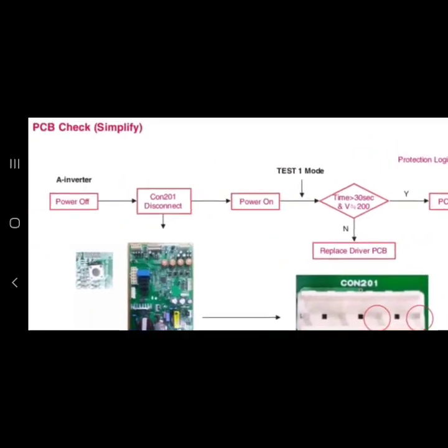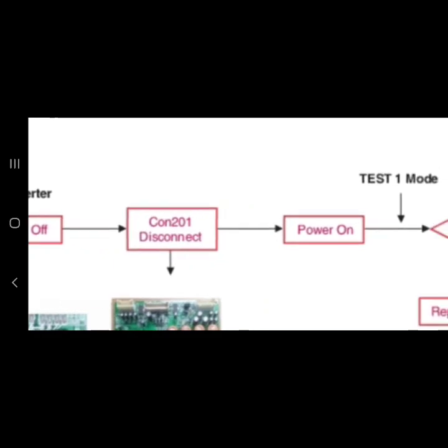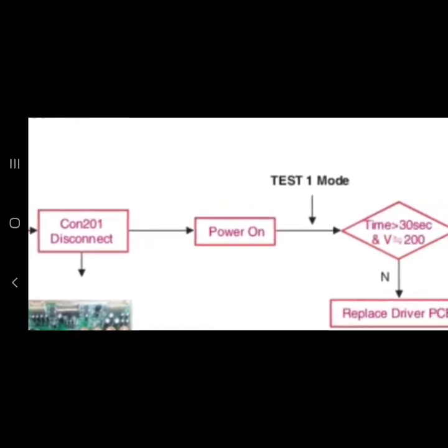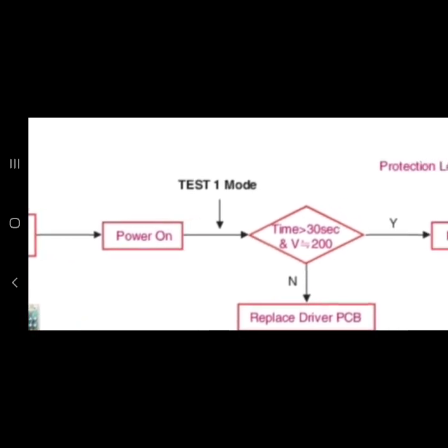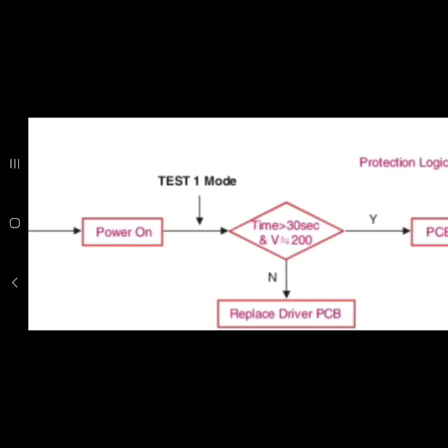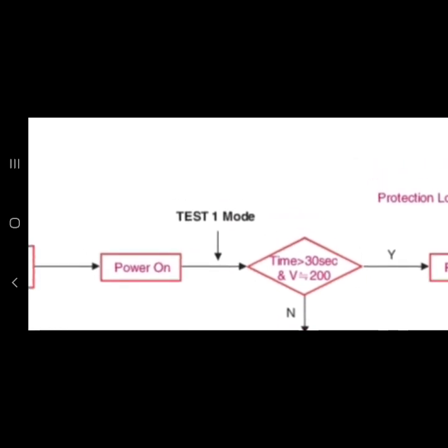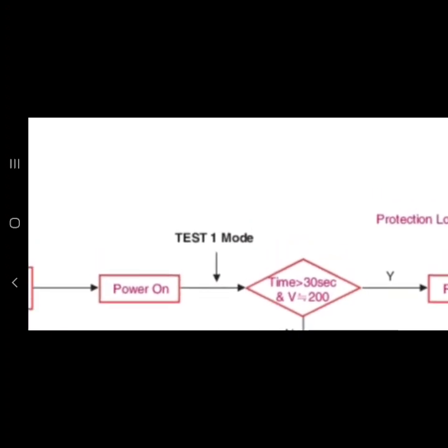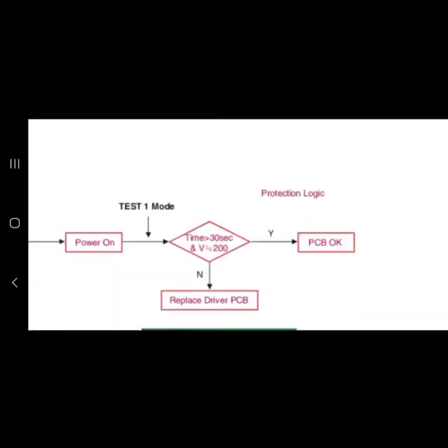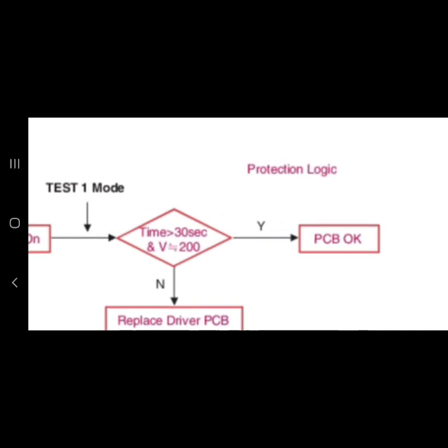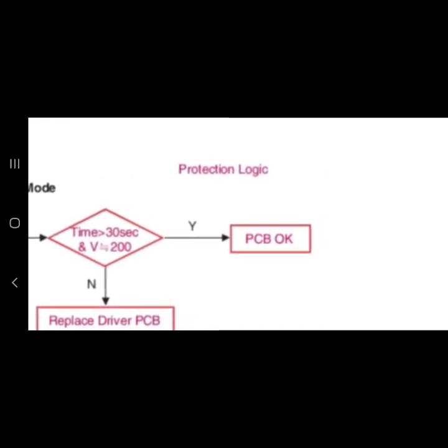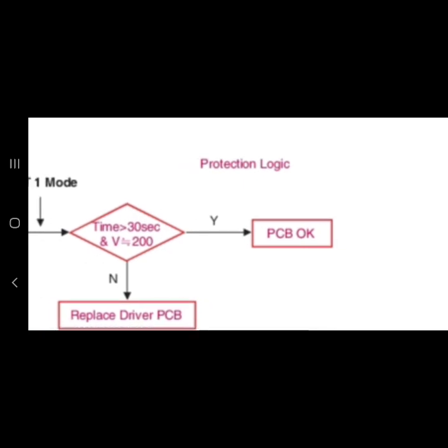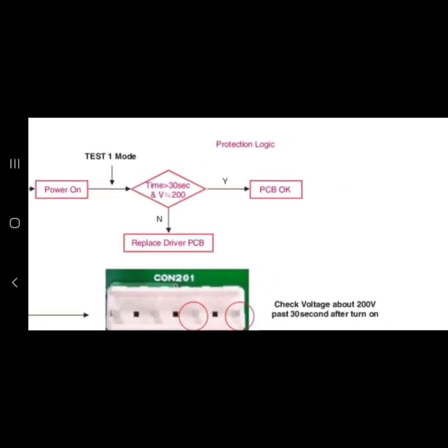Let's think about this. Again, we're going to power off step one, hook up our leads to Con201, which is short for connector 201. We're going to power on the unit and then after we power on the unit for 30 seconds, we're going to enter test one mode. Once we do that, within 30 seconds we should have about 200 volts. Now if yes we do have the 200 volts, then our PCB or printed circuit board is okay. But if we don't, then we need to replace the driver PCB, which is basically the whole board.